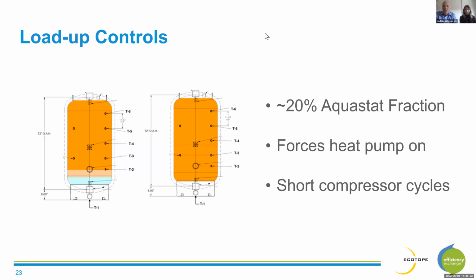And then before those peak demand periods, those shed periods when we want to shed load, instead of looking at that temperature sensor that's 40% of the way up the tank, we look at the one that's way down at the bottom. And that forces the heat pump to come on much sooner and charge the tank all the way up before we enter that shed period. And we wouldn't want to do this all the time, like run the heat pump with a temperature sensor all the way at the bottom of the tank, because it would lead to these short compressor cycles. It would cycle the heat pump on and off a lot. But we want to just do that in the period of time before the shed, so that we know that we enter that shed period with a fully charged thermal storage battery.